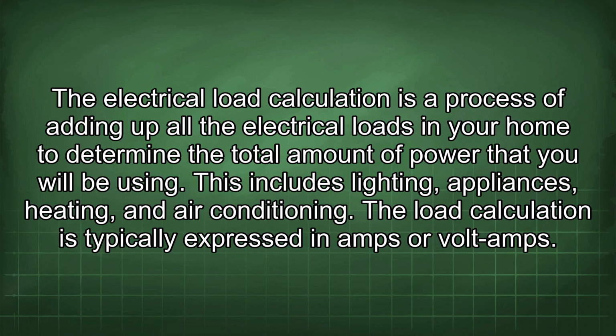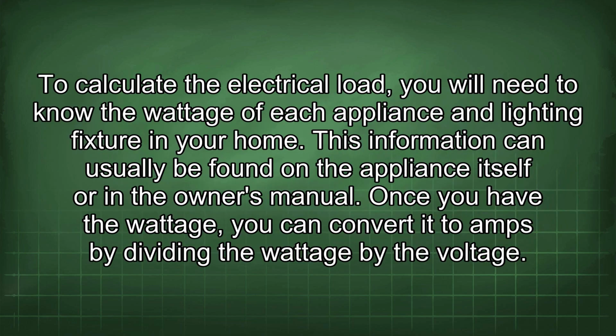The load calculation is typically expressed in amps or volt amps. To calculate the electrical load, you will need to know the wattage of each appliance and lighting fixture in your home. This information can usually be found on the appliance itself or in the owner's manual. Once you have the wattage, you can convert it to amps by dividing the wattage by the voltage.